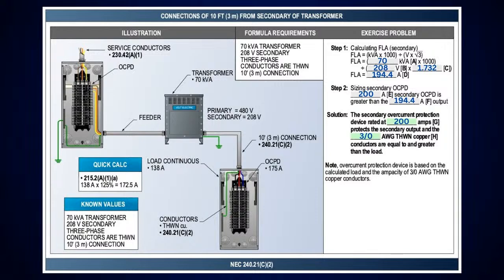And just letting you know, you can't pipe to a transformer. Yeah. And if I go over there for a 200 amp overcurrent protection device, it tells me I have to run based on that size overcurrent device per table 310.16, and I pick up the 75 degree C terminals. It's going to tell you need at least a 3-aught conductor. Nice. Okay. And that's how you size for the secondary side.